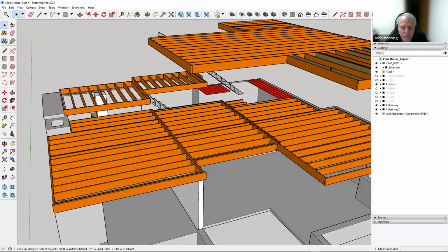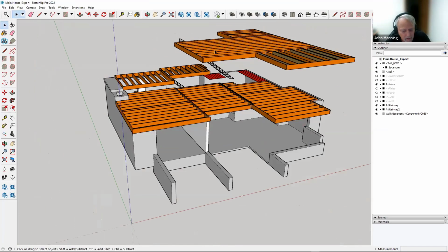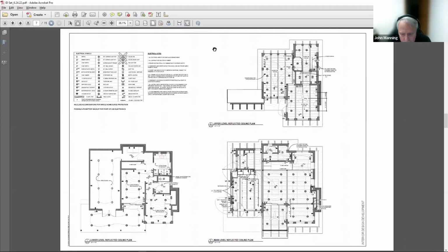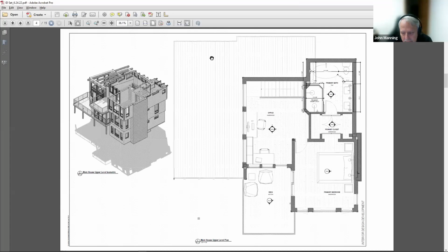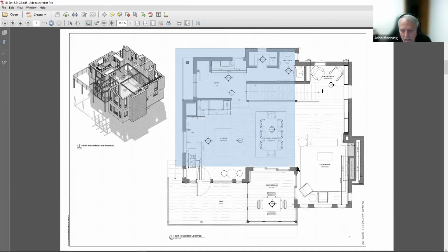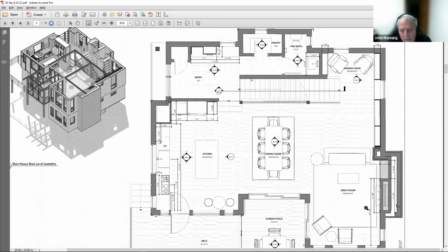Any thoughts about trying to get air up into the second floor? I can pull up a first floor plan if that would help. Let's see, I don't want the reflective ceiling. If we blow this up, are there any opportunities to get a soffitted vertical riser?